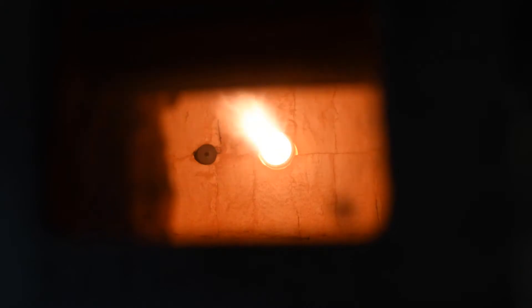Our regenerative system cycles between two burners. When one burner is firing, the other is exhausting. During the firing cycle, the burner will be using energy stored in its heat exchanger to preheat the combustion air.